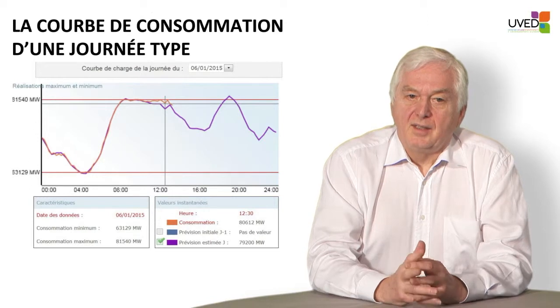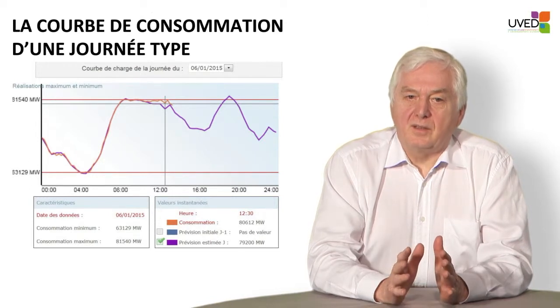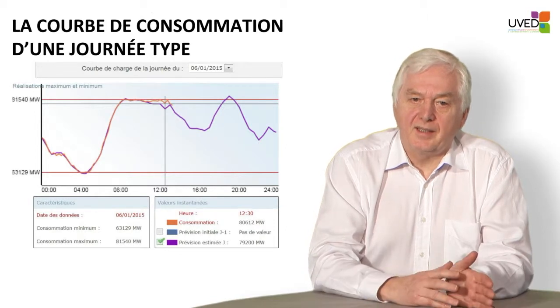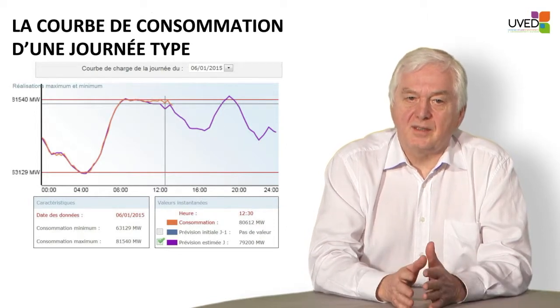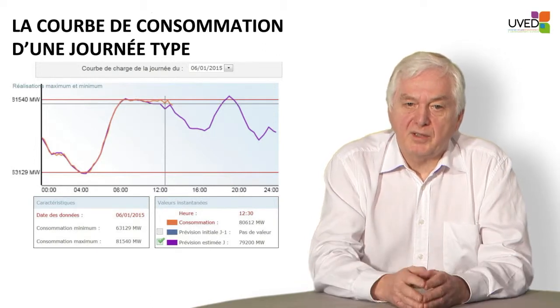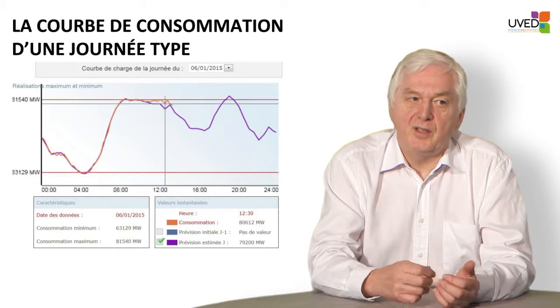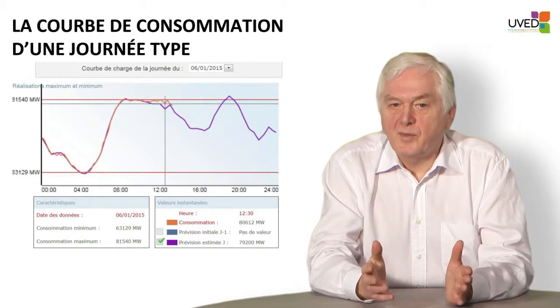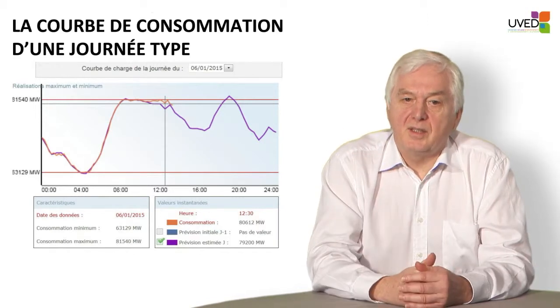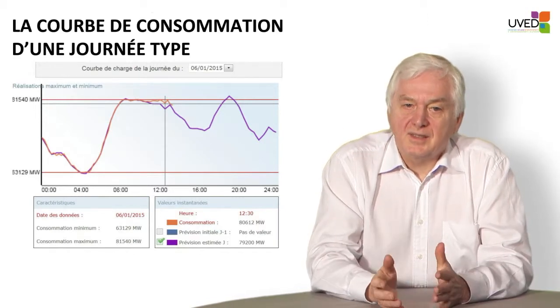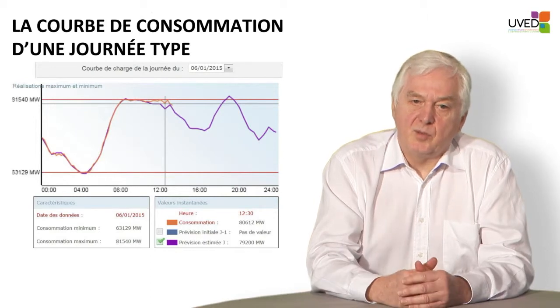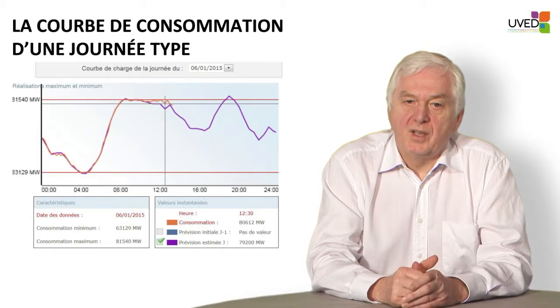So 15,000 megawatts must be found in less than three hours. Bear in mind that consumption must match production and production must match consumption — at any given time, production must follow consumption. We can't ask people to call before they switch on their coffee machine, and yet everybody does that more or less at the same time, and industrial plants start operating. So hydroelectricity can help mitigate the peak effect.